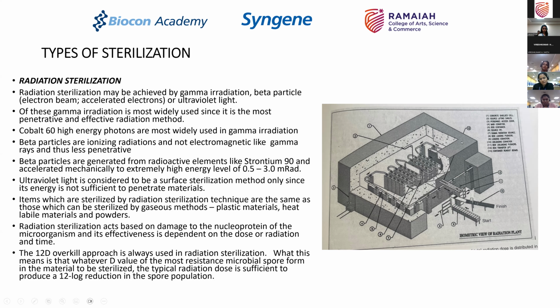Because first of all, you may not have sufficient material or quantum to gamma irradiate every day, even if you are manufacturing a batch every day, because the investment on this equipment is very, very high. And therefore, when you invest in a gamma irradiation facility, you should be doing multiple batches a day to make this cost effective.